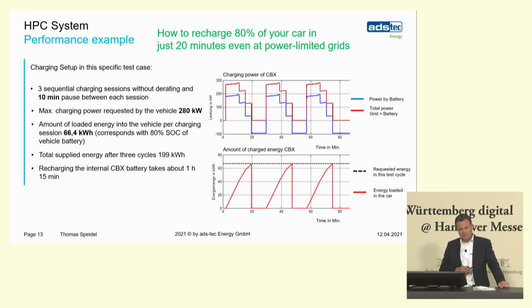Here we see three sequential charging sessions without any derating, with a 10 minute pause between each session, shown in the diagram on the right. The power from the battery is shown in blue, and additional power comes from the grid, since we have some grid power available. The red line shows the sum — the total available power from battery and grid — which goes up to 280 kilowatt in this case, as requested by the car.